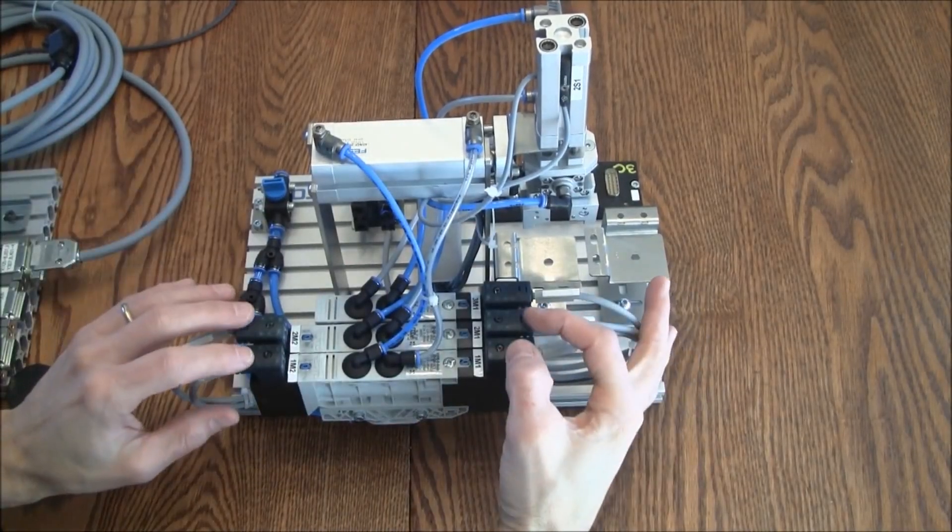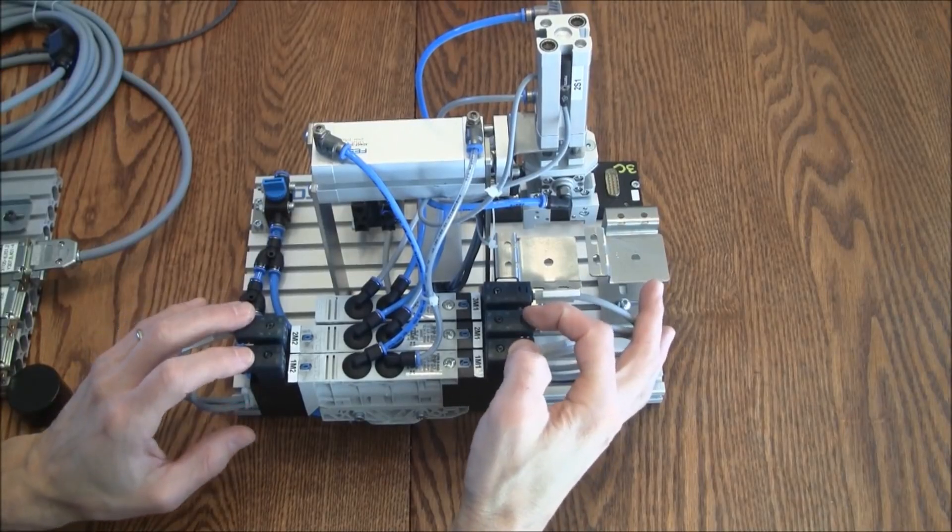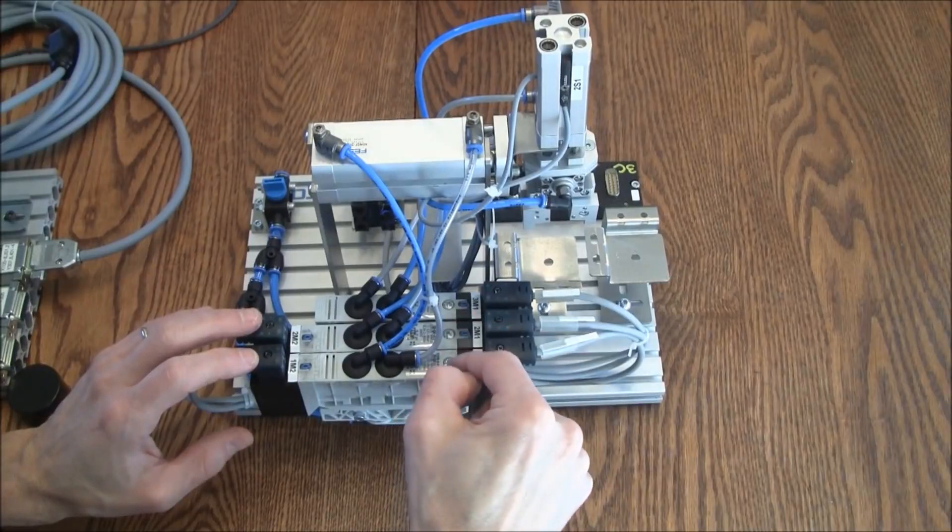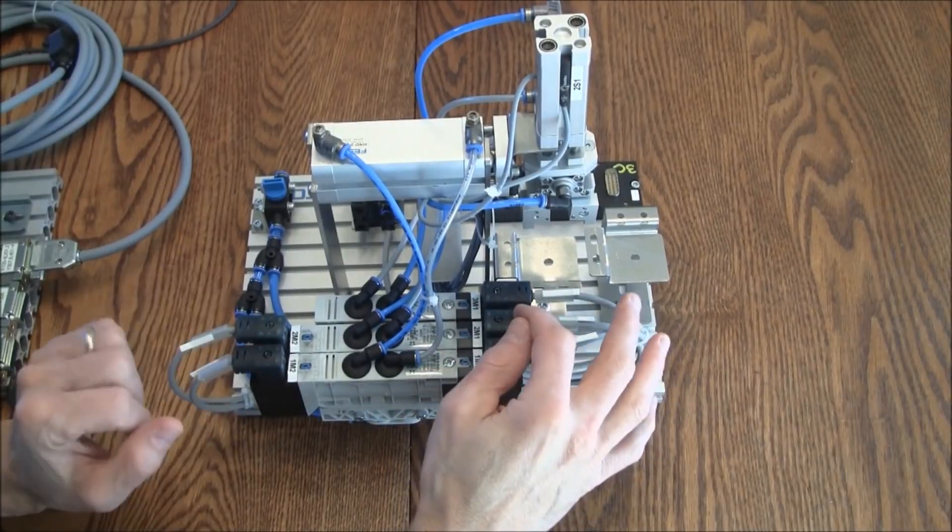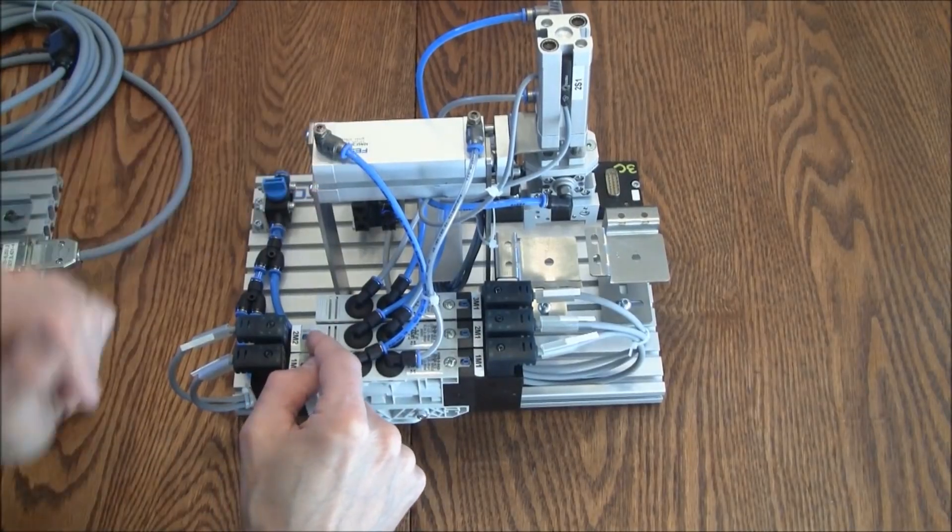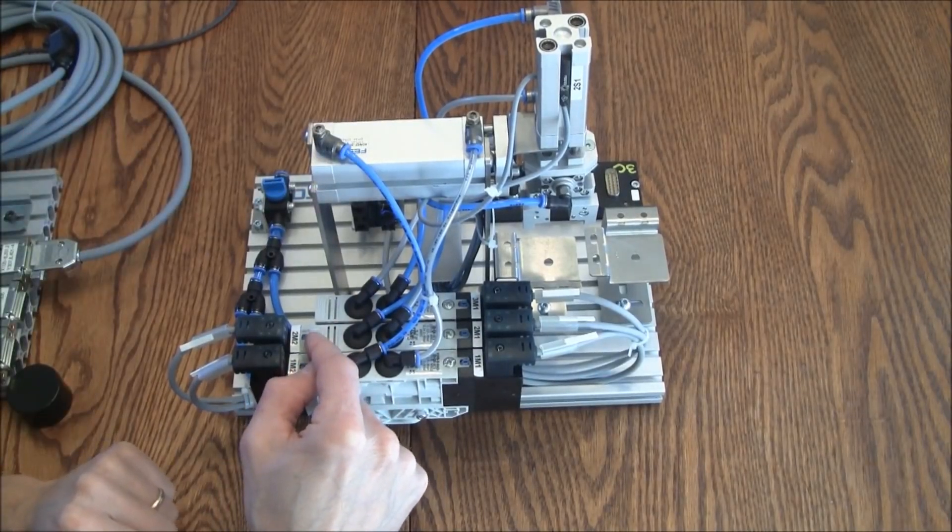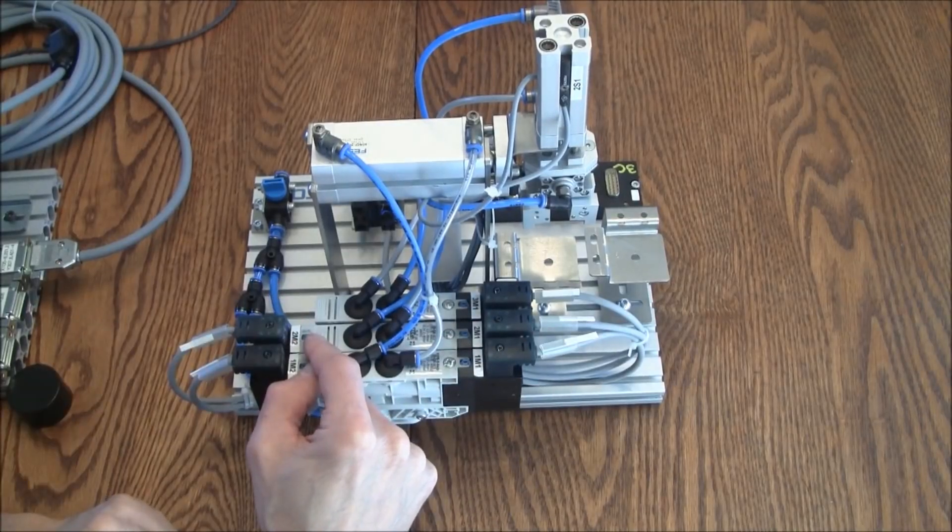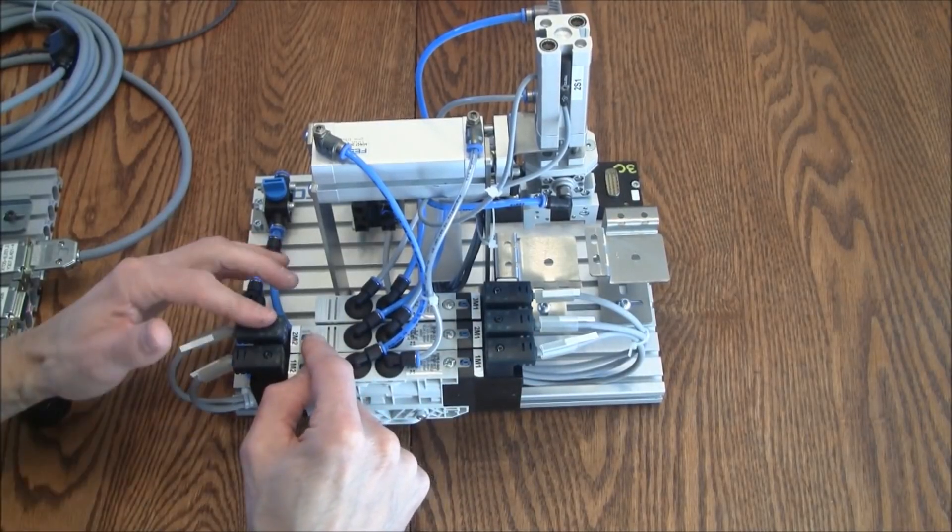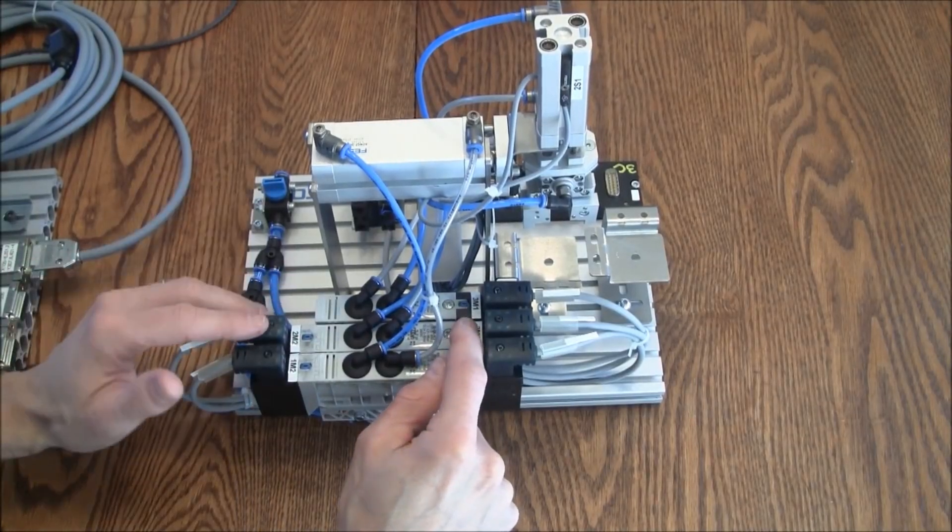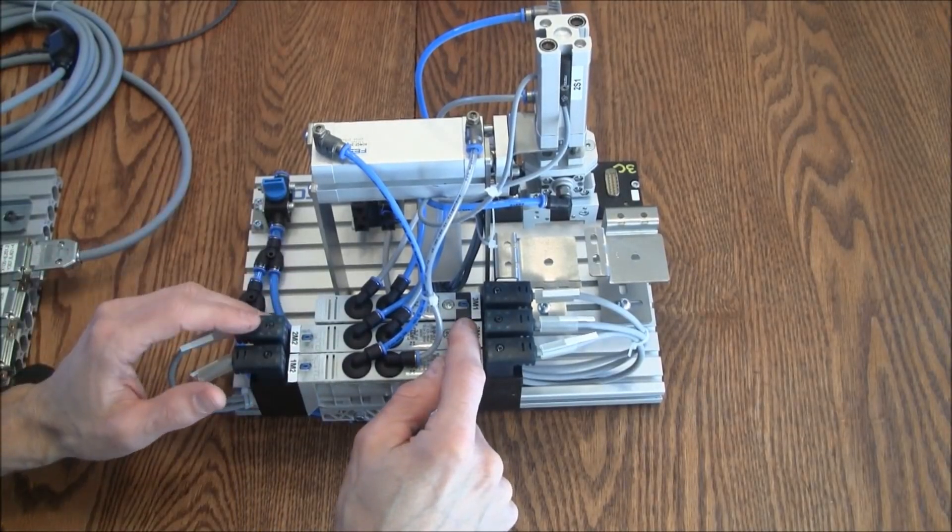With these double solenoid controlled valves and cylinders, they're also four two ways. When I energize one of the solenoids the spool will shift and the cylinder will move into a particular position. When I de-energize it, it will stay in that position because of a detent. When I energize the opposing solenoid, that spool will shift causing that cylinder to move into the other position.